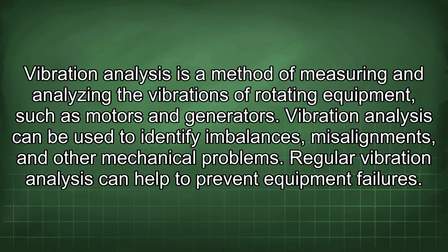Thermography is a method of using infrared cameras to detect temperature differences in electrical equipment. Thermography can be used to identify overheating components, which can be a sign of a potential problem. Regular thermographic inspections can help to prevent electrical failures. Vibration analysis is a method of measuring and analyzing the vibrations of rotating equipment, such as motors and generators. Vibration analysis can be used to identify imbalances, misalignments, and other mechanical problems. Regular vibration analysis can help to prevent equipment failures.